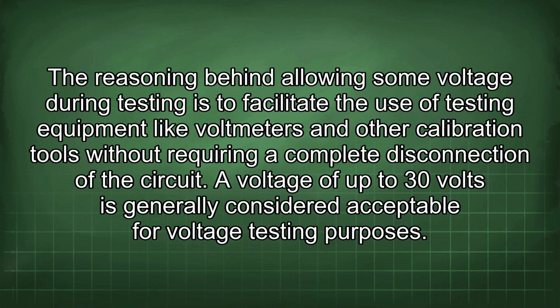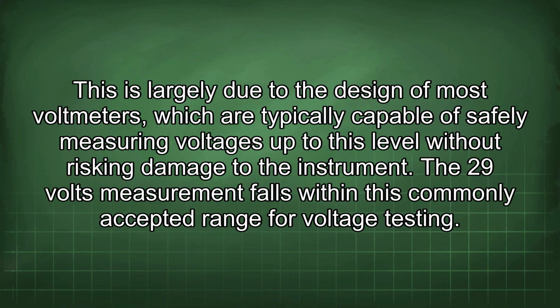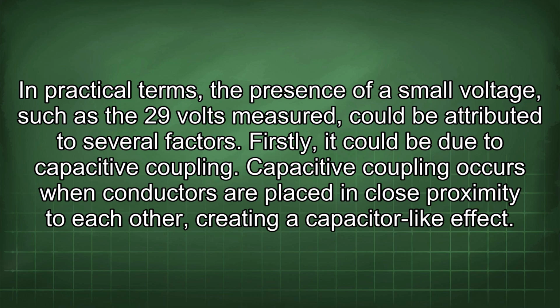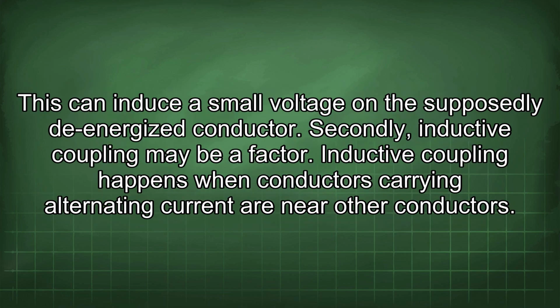A voltage of up to 30 volts is generally considered acceptable for voltage testing purposes. This is largely due to the design of most voltmeters, which are typically capable of safely measuring voltages up to this level without risking damage to the instrument. The 29 volts measurement falls within this commonly accepted range for voltage testing. In practical terms, the presence of a small voltage, such as the 29 volts measured, could be attributed to several factors. Firstly, it could be due to capacitive coupling. Capacitive coupling occurs when conductors are placed in close proximity to each other, creating a capacitor-like effect. This can induce a small voltage on the supposedly de-energized conductor.